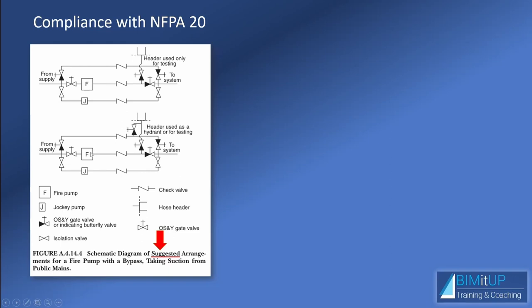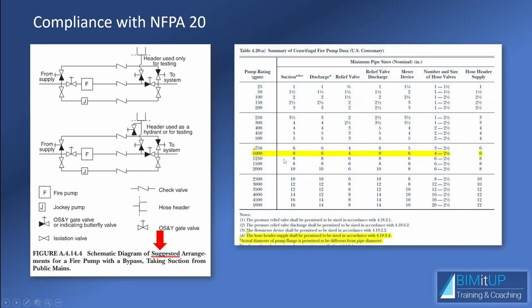See, this would be the main fire pump. Then out of the fire pump, you could test at high pressure, but you could also go from the bypass and connect to that test header and just close this other valve. So NFPA 20 also lets you know what suction, discharge, and other piping sizes have to be. So for our example, we're gonna have a 1,000 GPM fire pump. So our suction line is gonna be 8 inches. The discharge is gonna be 6 inches.